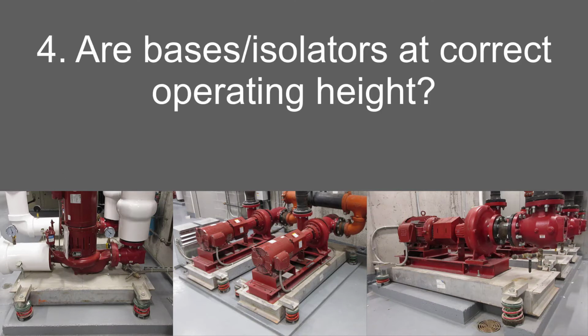Are the bases isolators at the correct operating height? No, none of the bases had a full 2-inch clearance under the entire base. There are no shims and it's questionable if any were used. This has led to debris getting caught and hidden under the bases, which may be the primary reason why some of the isolators don't appear to have much load on them. This is the primary problem with this project.